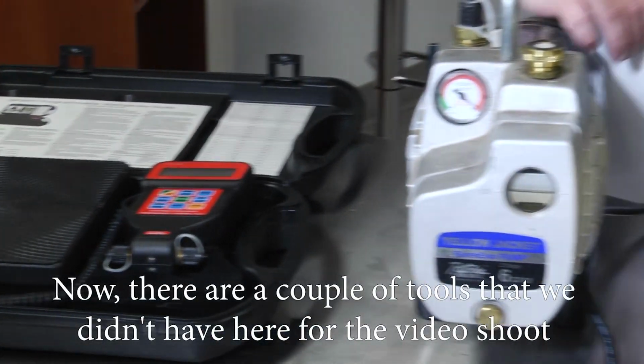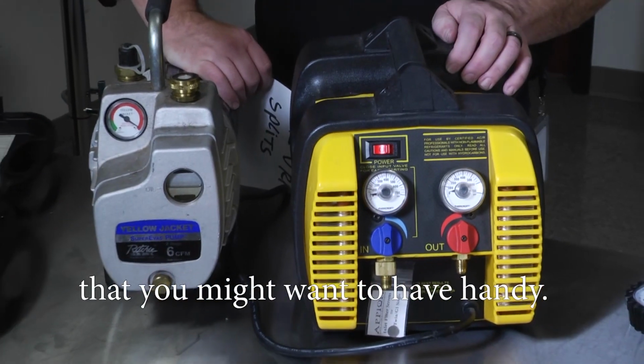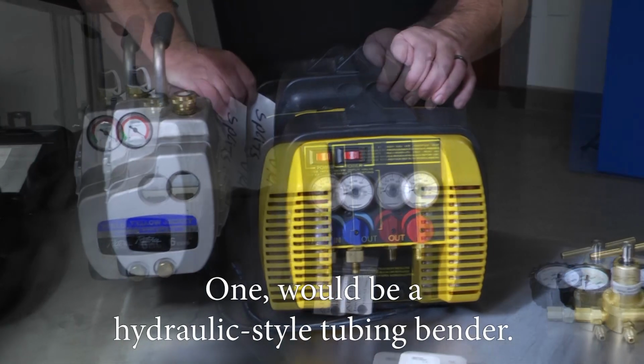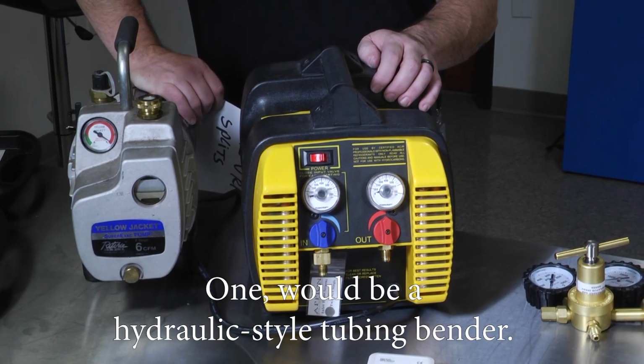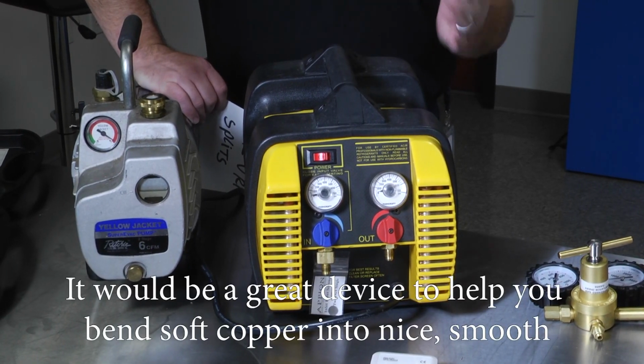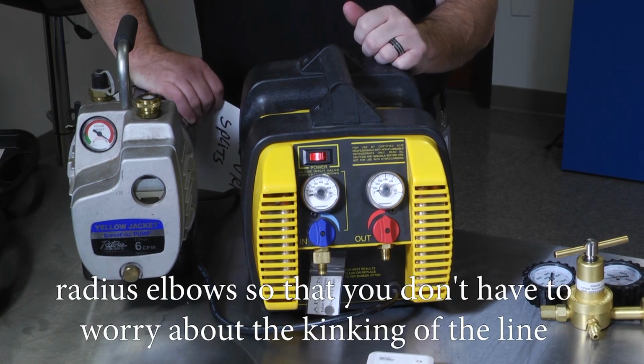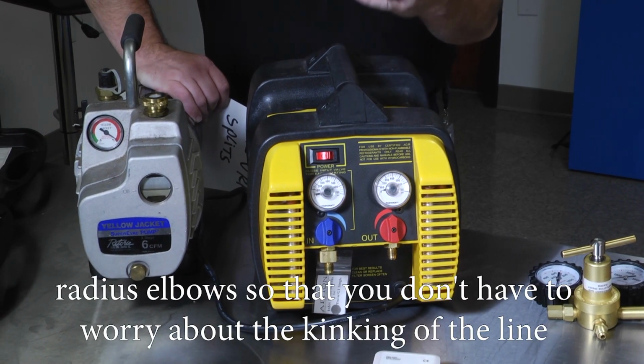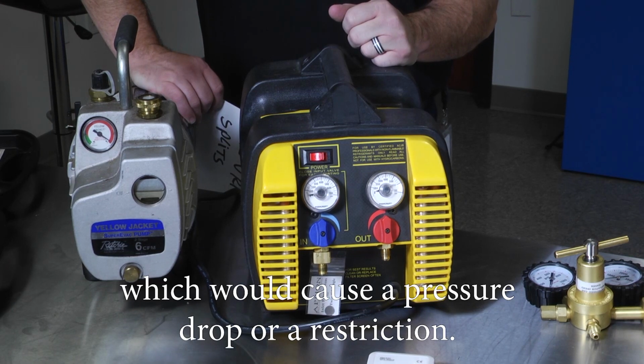Now there's a couple tools here that we didn't have for the video shoot that you might want to have handy. One would be a hydraulic style tubing bender. Would be a great device to help you bend soft copper into nice smooth radius elbows so that you don't have to worry about kinking of the line, which would cause a pressure drop or a restriction.